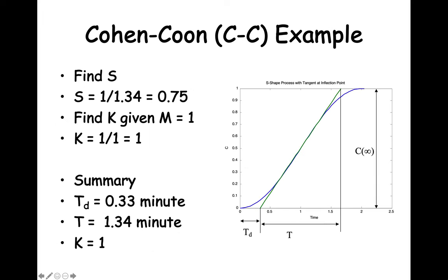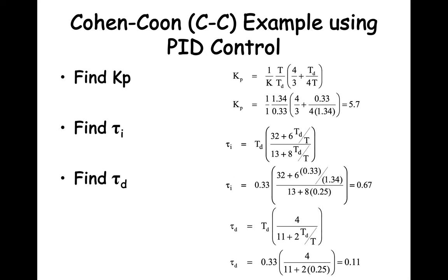We can calculate the tangent slope S, which is 1 over T. We get 1 over 1.34, so the slope is 0.75. We can calculate the process steady state gain K equal to C infinity divided by M. Both C infinity and M equal 1, so K equals 1. We know that the transport lag time Td equals 0.33 minutes, the process time constant T equals 1.34 minutes, and the process steady state gain K equals 1. Assuming PID control, we use these equations to find Kp, tau i, and tau d. We find that Kp equals 5.7, tau i equals 0.67, and tau d equals 0.11.